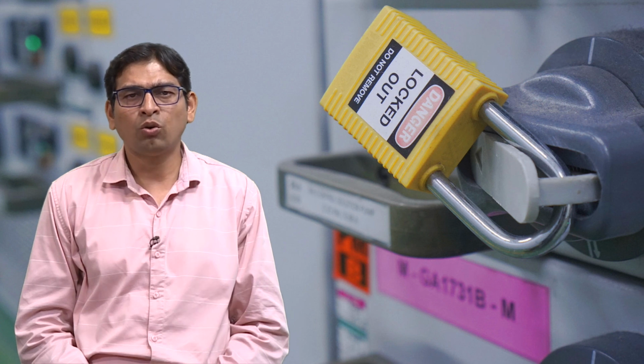Move the switch to the off position, then use a padlock and tag and the appropriate lockout tagout procedure to isolate the energy sources. Remember, most boxes have two places where you can attach a lock. One will lock the box shut while the other will lock the power off. Make sure that you put your locks on the correct one.